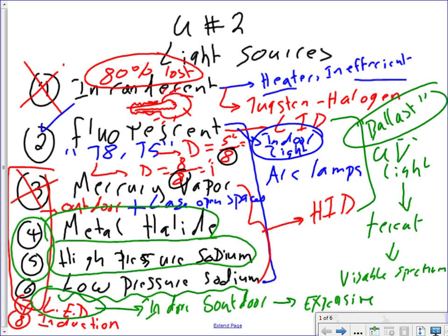If you go to page 20, please, it gives you the lumen and life characteristics of high intensity discharge (HID) lamps. If you look at the first one, the lumen maintenance curve, you can see how they have different characteristics. I want to bring to your attention the last one, high pressure sodium. After 24,000 hours, the fixture will go down only to 80% of its lumens. If that lamp is supposed to give you 100 lumens, after 24,000 hours of operation it will give you 80. That's good, it lost only 20. These curves are a major part of deciding how to choose a lighting fixture for a certain application. When you put in a fixture, you need to take into consideration a lot of things.